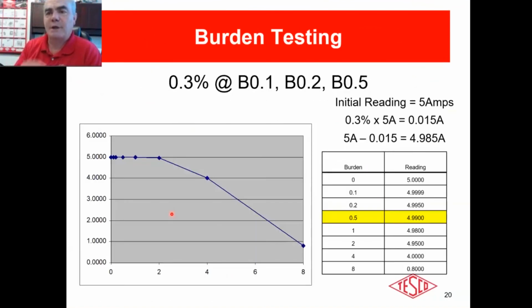I want to come down to here. So this is the accuracy of that transformer. I did a whole bunch of readings at 0 burden. I put in 400 amps, for example, and I got 5.000 out. I read it to 4 significant digits, and I got that. At 0.1, I got 4.999, 0.2, 4.995, 0.5, 4.99.